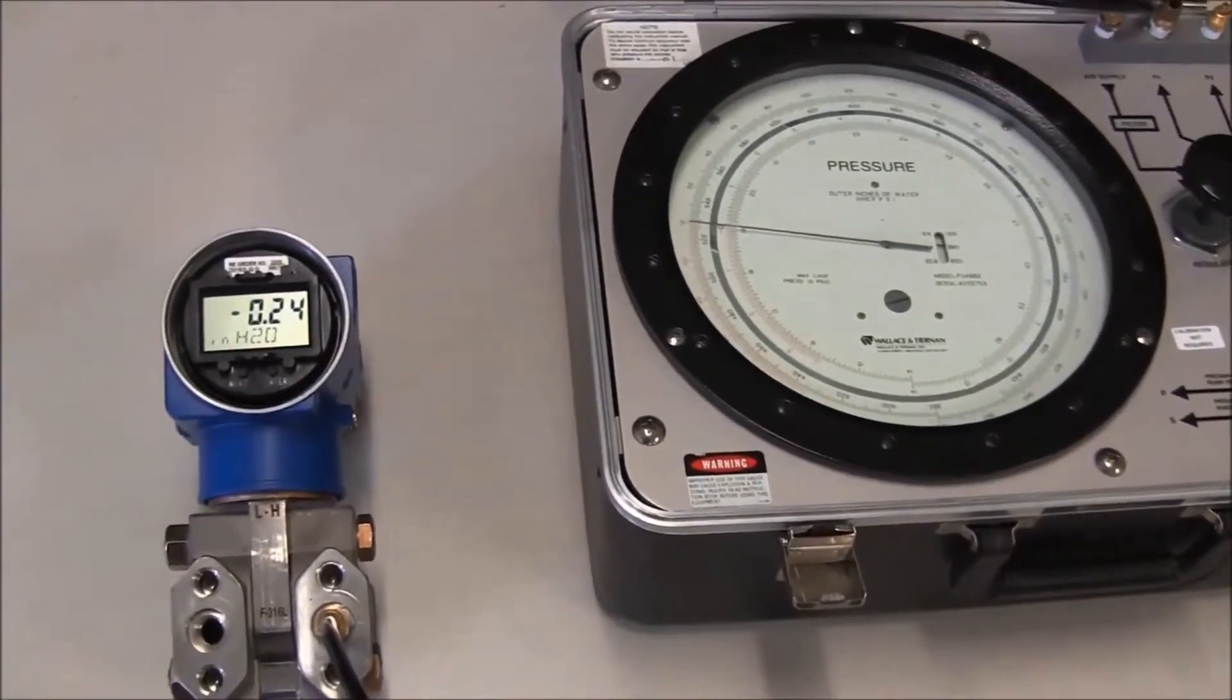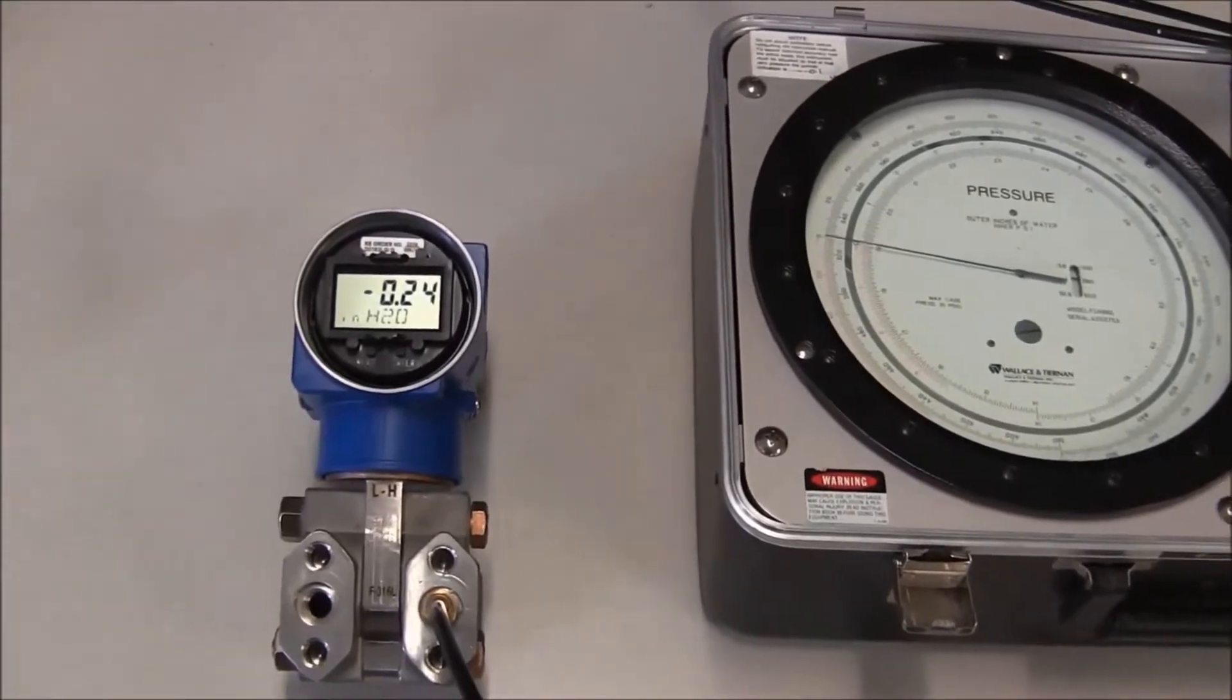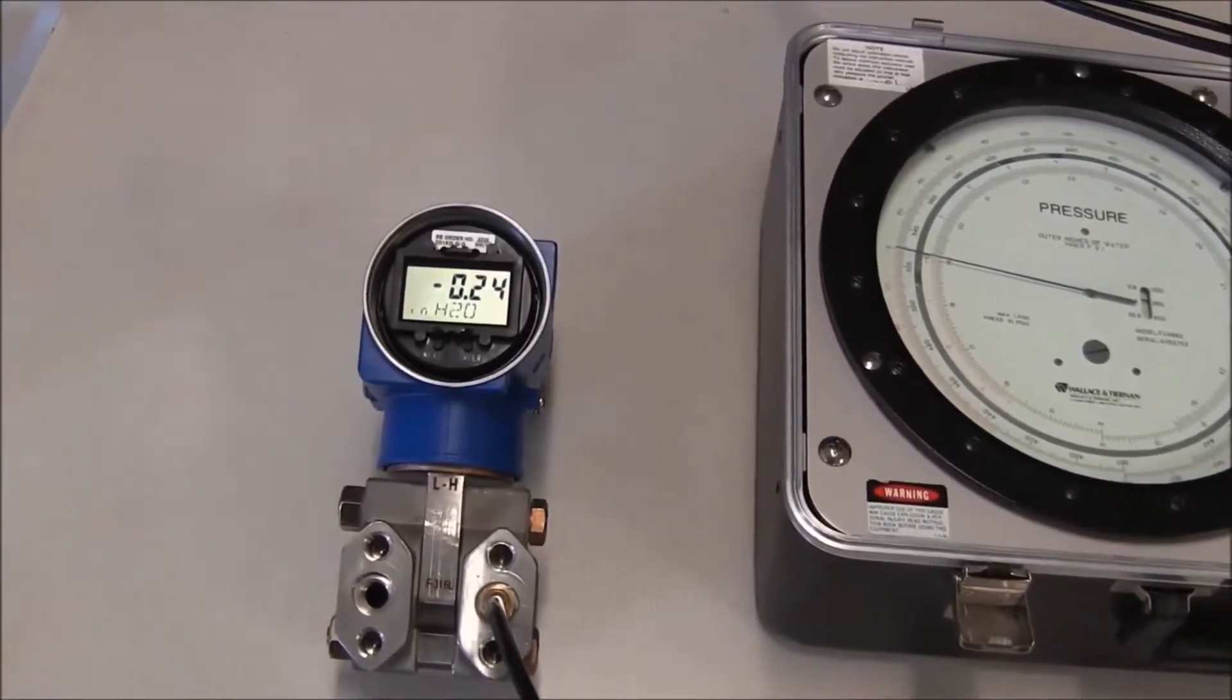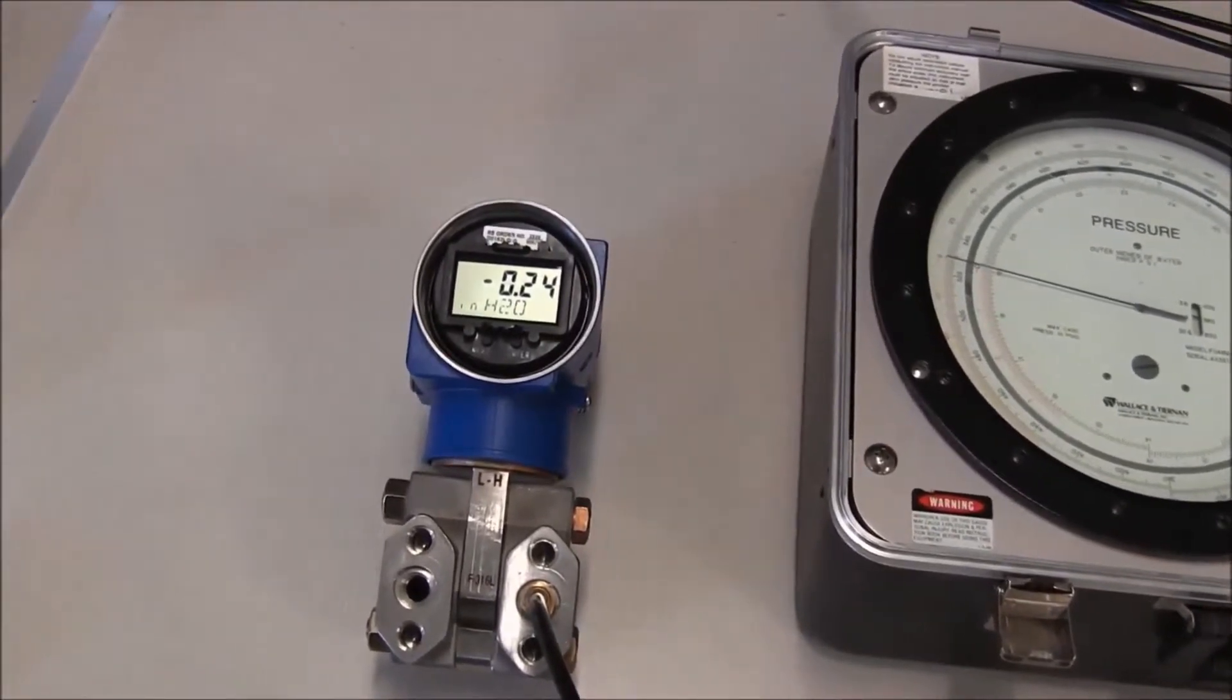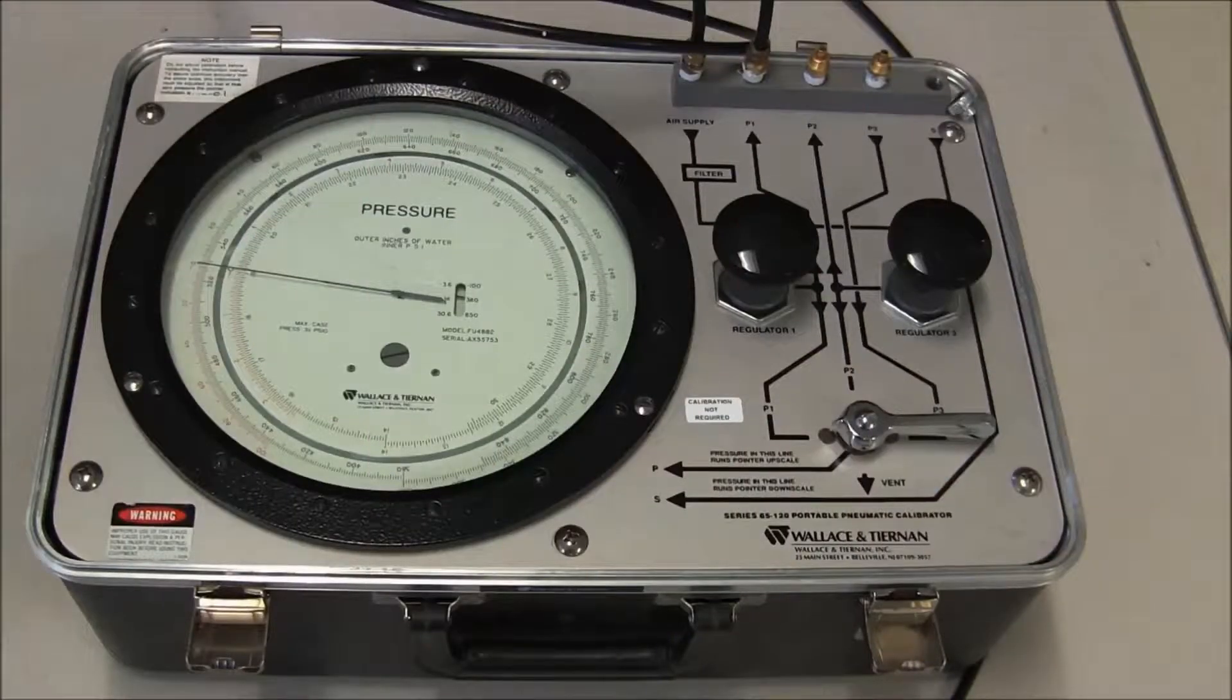In the following demonstration, we will perform a two-point calibration of the IDP10-T transmitter. This will require the use of an accurate pressure calibrator.